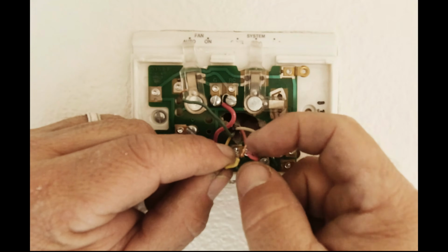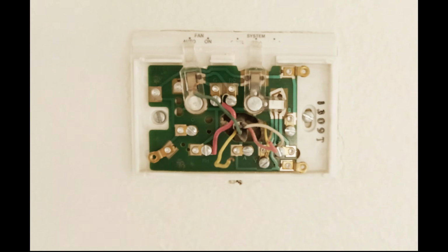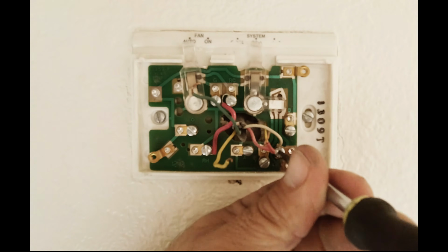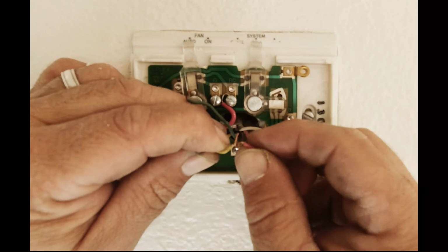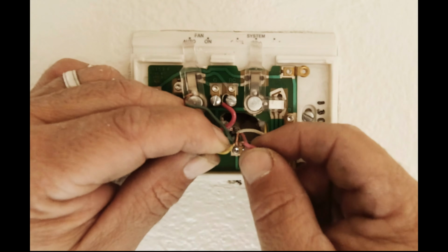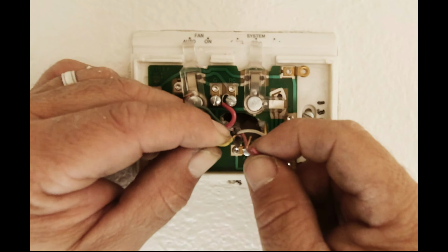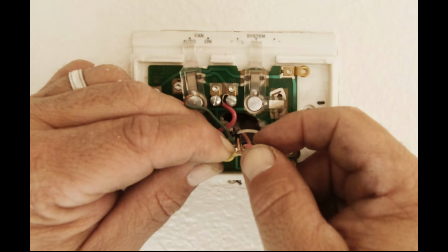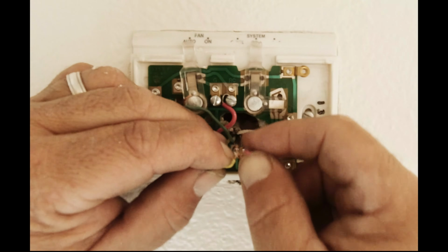But this was a good test because at this point, I knew for sure that there was something going on up in the unit somewhere. It had nothing to do with the thermostat, because I was making the connection and the AC was not kicking on the compressor. I kept on trying it, thinking it was something wrong, but of course, later on I found out it was just a tripped breaker. It could have been a capacitor up on the unit. It could have been a burnt breaker or a burnt fuse, but it wasn't any of that. Somebody had lowered it. I'm trying to figure out what's going on. Of course, it didn't kick on. I found out later it was just that breaker.